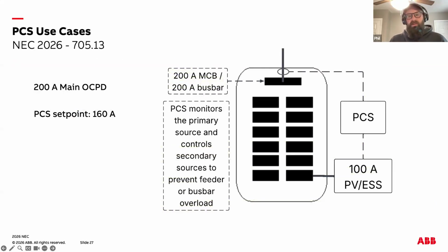In this diagram, we're looking at a service equipped with a 200 amp main breaker feeding a 200 amp rated bus bar. Under the traditional 120% load side interconnection rule in 705.12, the maximum PV or ESS system you could backfeed into this panel would be limited to a 40 amp breaker, which often restricts system size and forces costly equipment upgrades. Section 705.13, however, opens the door to a different approach. By using a listed power control system, the installation can actively monitor and control both power producing sources and connected loads to ensure the feeder or bus bar is never overloaded.